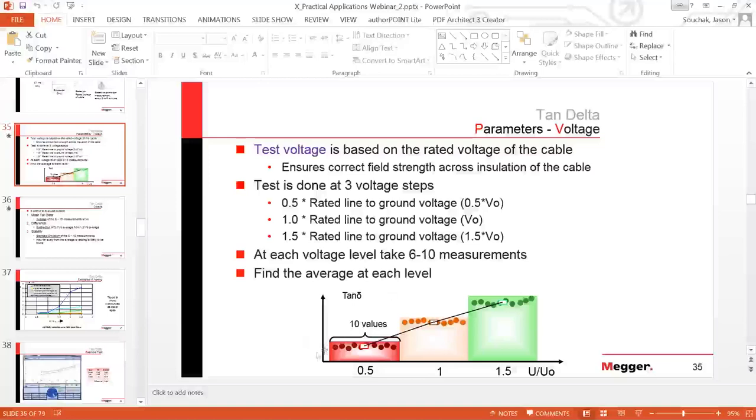We do that to get that stability measurement, really. If you took just a single point, you can't make a stability assessment off of it. But if you took multiple points, like I show here, you can see if they're stable. If you have 6 points that all come back to be the same value or very, very close, you have very good stability. If there's range there, then you have more and more poor stability.